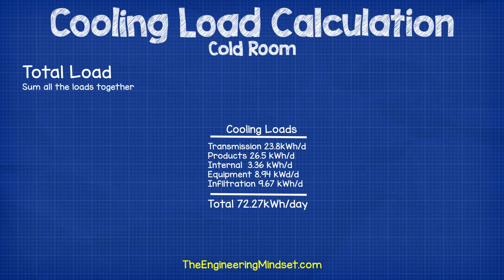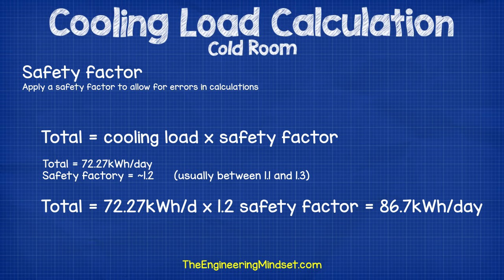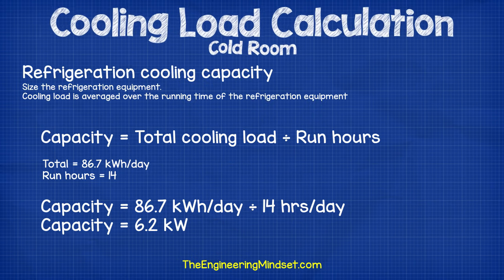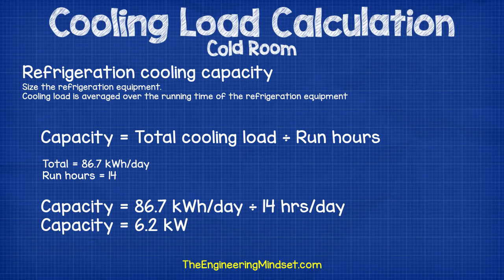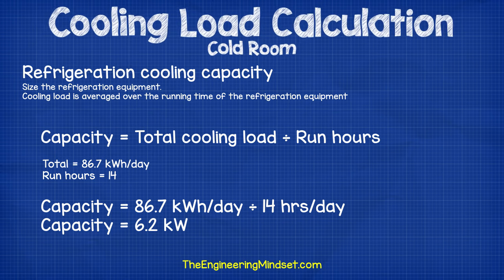Now we sum up all the calculations to get a total cooling load of 72.27 kilowatt hours per day. We then apply a safety factor — typically 10 to 30 percent — to account for errors and variations from design. I've gone with 20 percent, multiplying by a safety factor of 1.2 to give a total cooling load of 86.7 kilowatt hours per day. To size the refrigeration unit, we divide the total daily cooling load by the estimated run time of 14 hours per day, meaning the refrigeration unit needs a capacity of 6.2 kilowatts to sufficiently meet our cooling load.